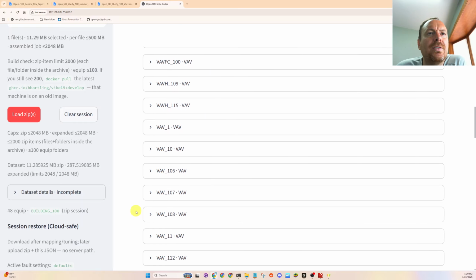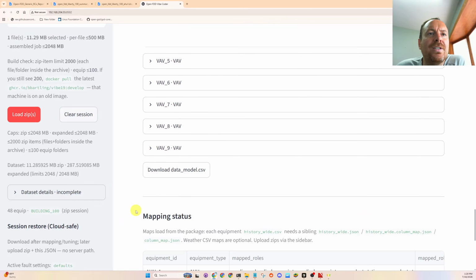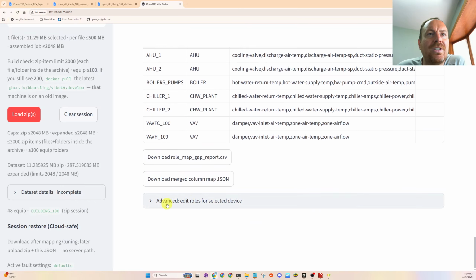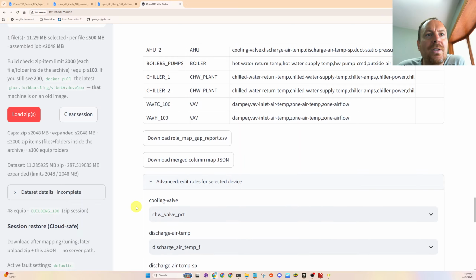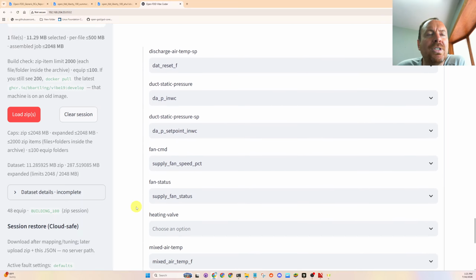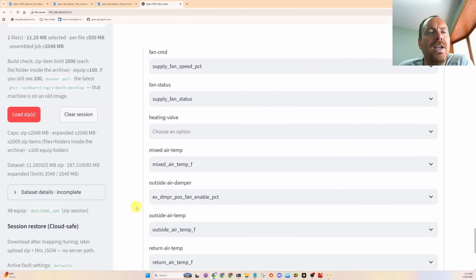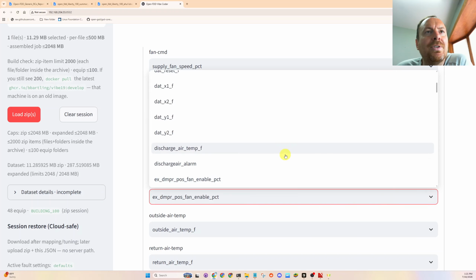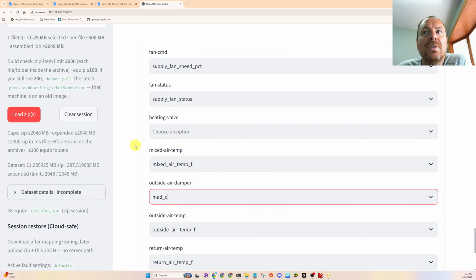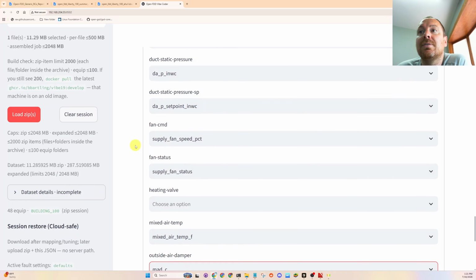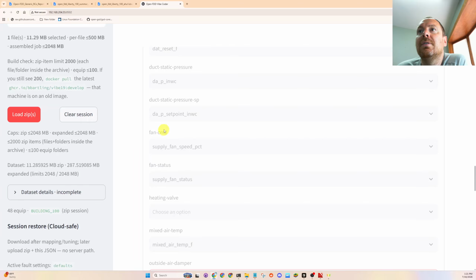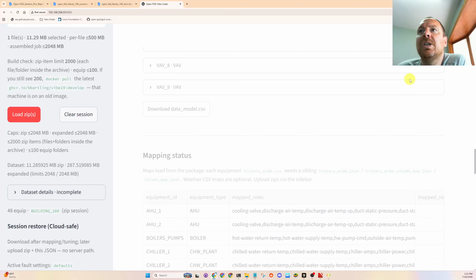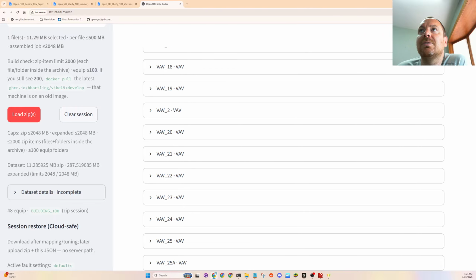Okay, so I do have some VAVs here, but this is advanced down here in the bottom. And then I am selected for air handling unit 1 and see my outside air damper. The AI mapped the wrong point to it. So MAD-C. So we have to change this. And it went to gray. So it's thinking.